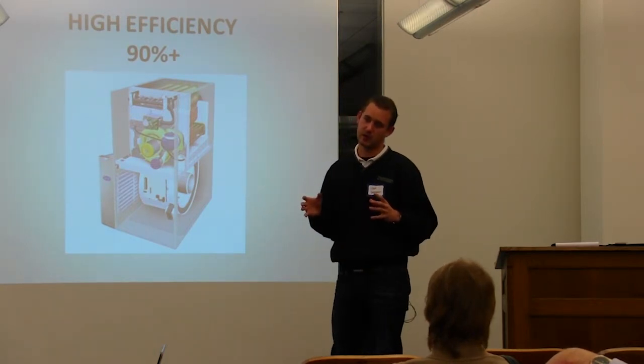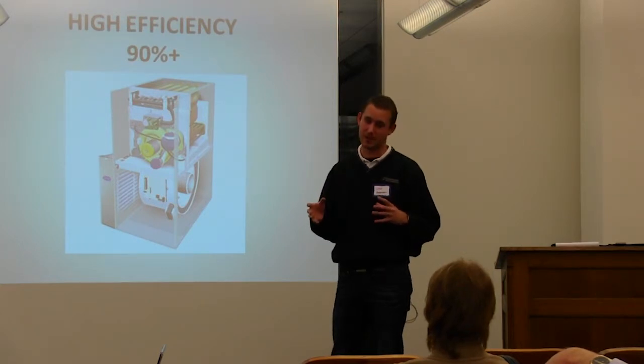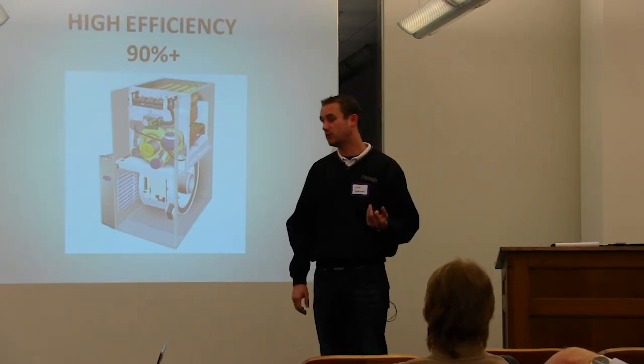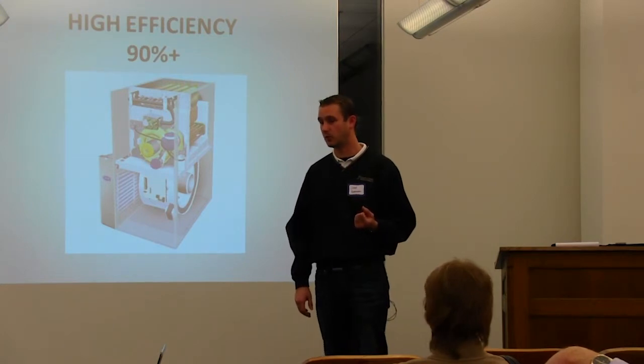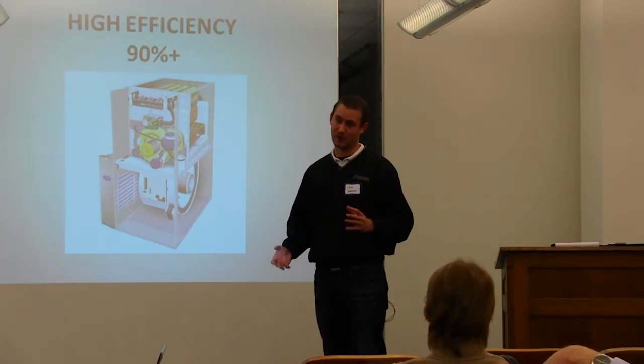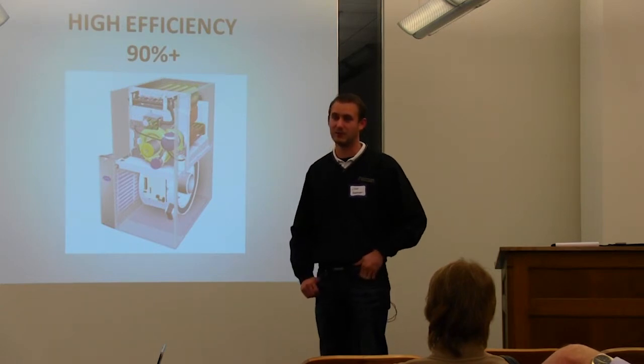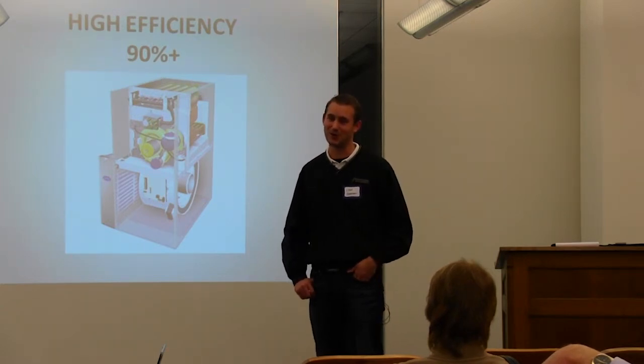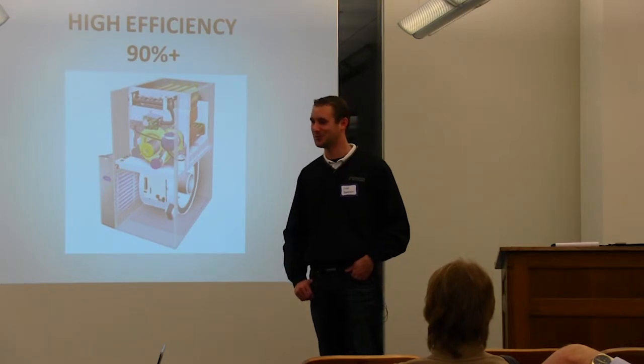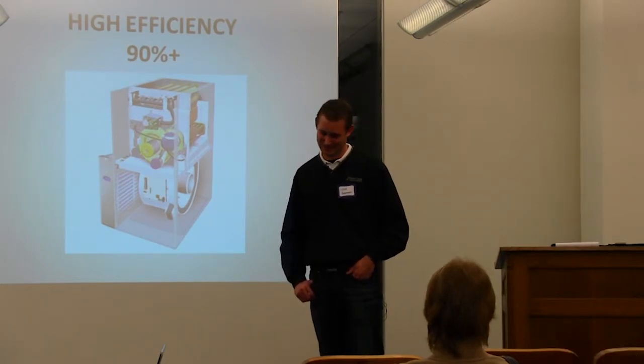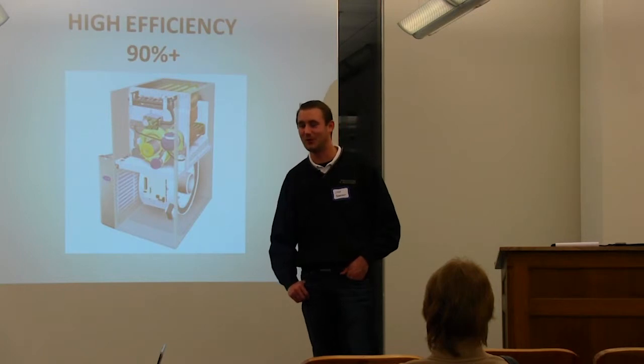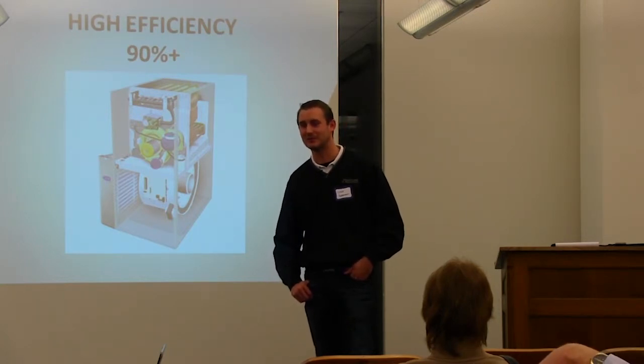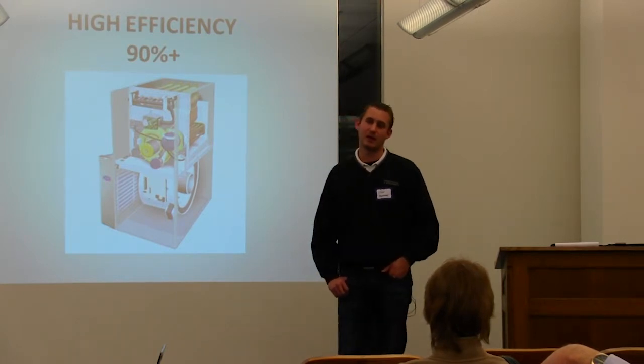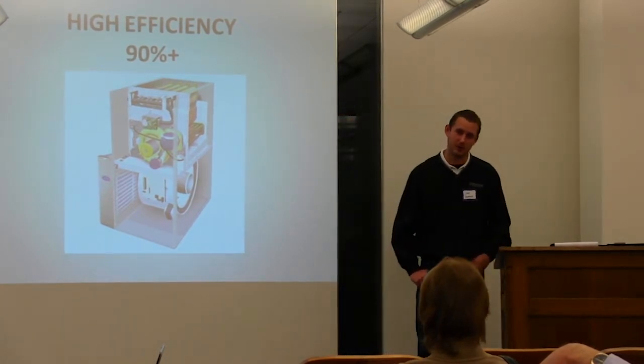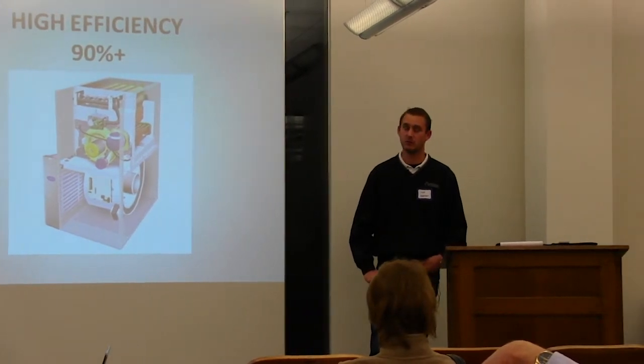You slide the entire blower out of the bottom, and then you've got anywhere between 3 and 8 wires going back to the control board. And if you're really good with wiring, anytime I take a blower off, even though I've got experience, I still snap a picture of the wiring before I start pulling wires off. There's nothing worse than sitting there going, I need to start from scratch and figure out where each wire goes, because even with experience, it takes a little bit of time. So, long story short, I wouldn't recommend it, but yes, you could do that with usually a 1/4-inch nut driver.